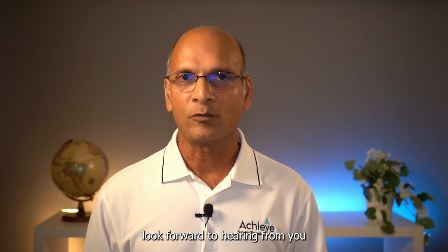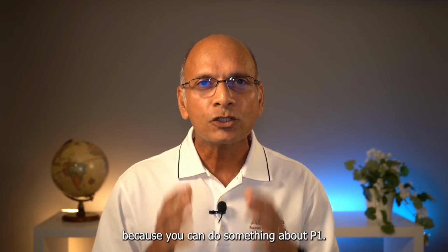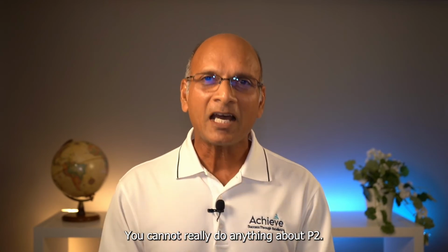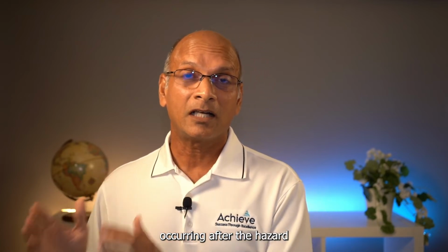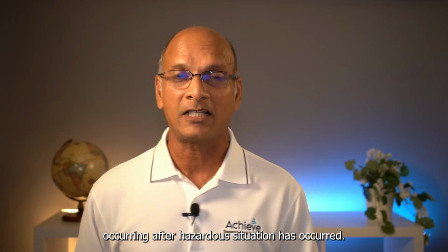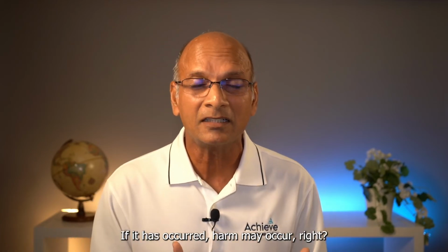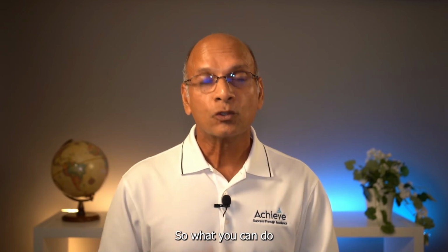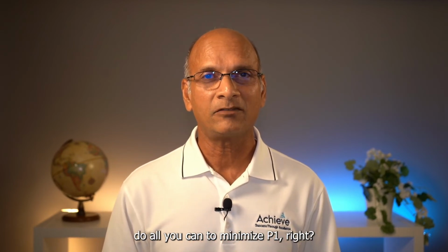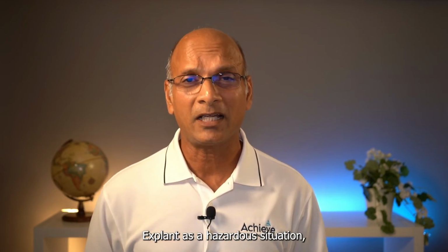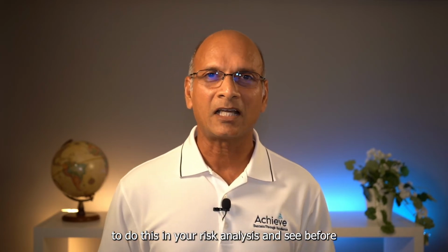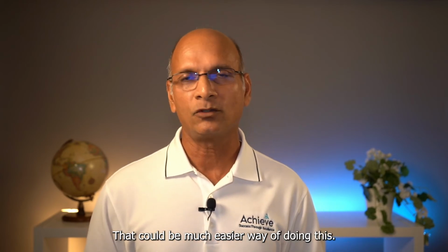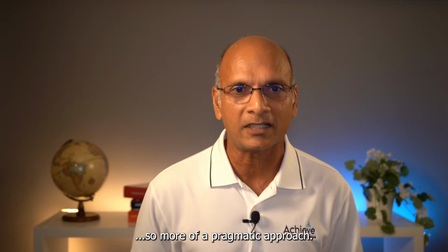Again, I look forward to hearing from you what your perspective is, because you can do something about P1. You cannot really do anything about P2, unfortunately. P2 is the likelihood of the harm occurring after the hazardous situation has occurred. If it has occurred, harm may occur, right? So what you can do from a manufacturer perspective, do all you can to minimize P1, right? And if you look at explant as a hazardous situation, that gives you a real way to do this in your risk analysis and see before and after easily. That could be a much easier way of doing this, so more of a pragmatic approach.